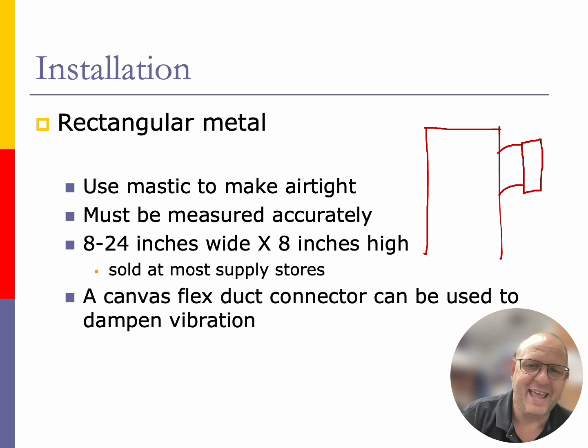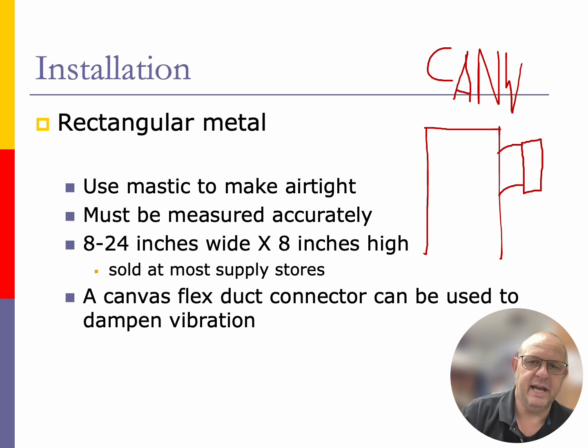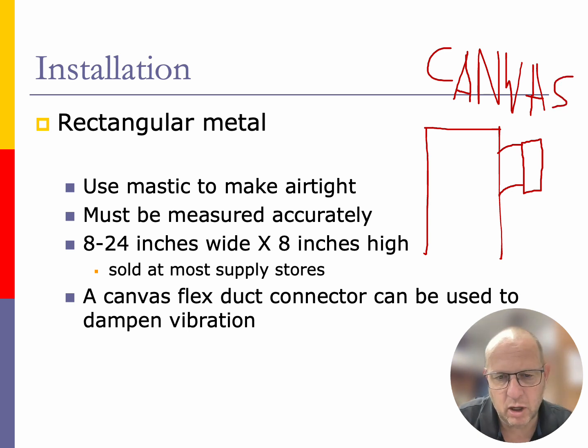And this is a type of canvas connector that will absorb the vibrations off of the furnace so that we are not transmitting the vibration and the noise down the entire stretch of ductwork on that system. And then we'll go ahead and hook it up to our ductwork as it's running down it. So that is a canvas connector right there on our particular ductwork, and it's there to stop the vibrations from the furnace from entering into the ductwork and running down and into the environment in which our occupants are.